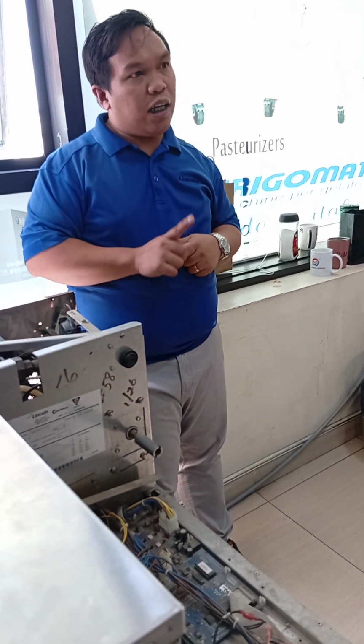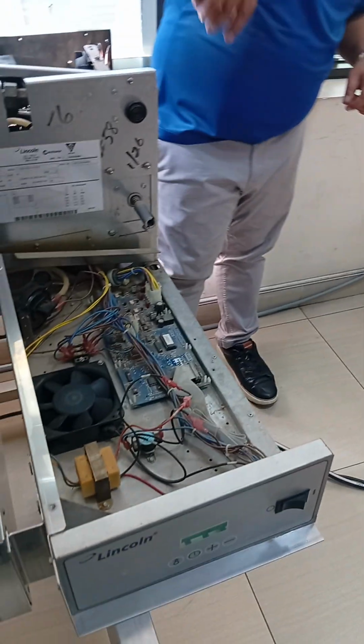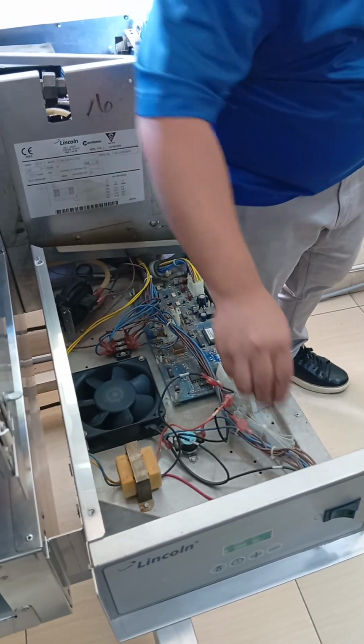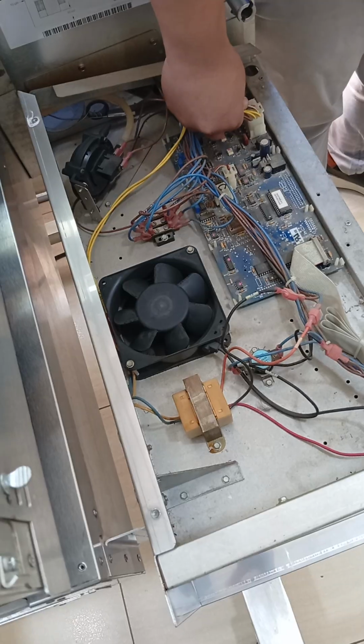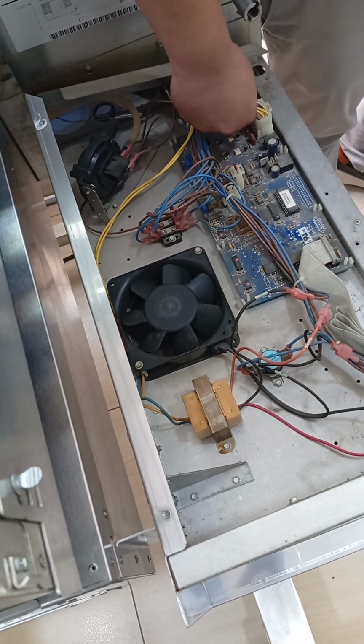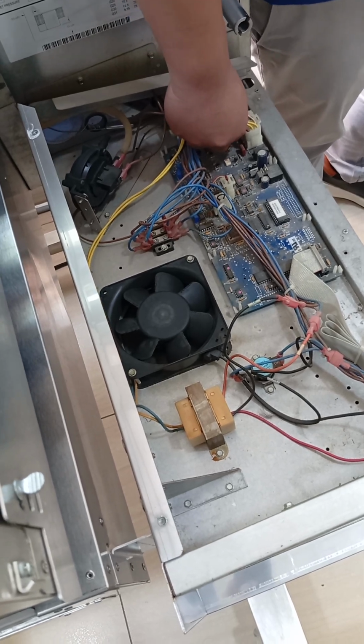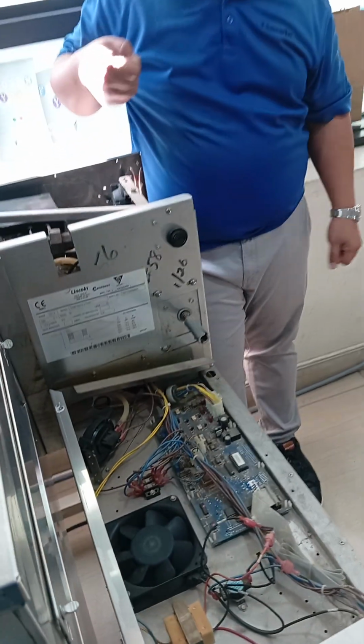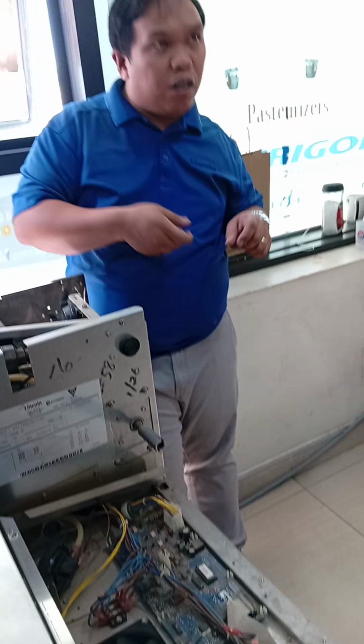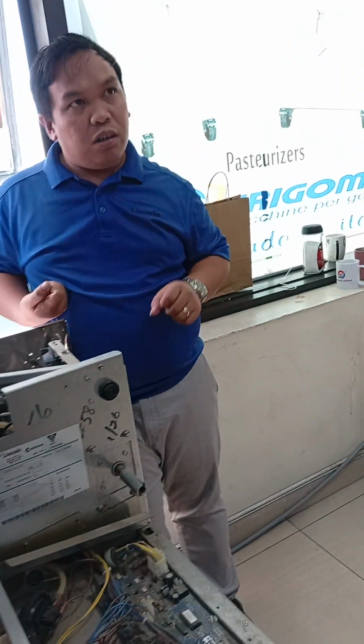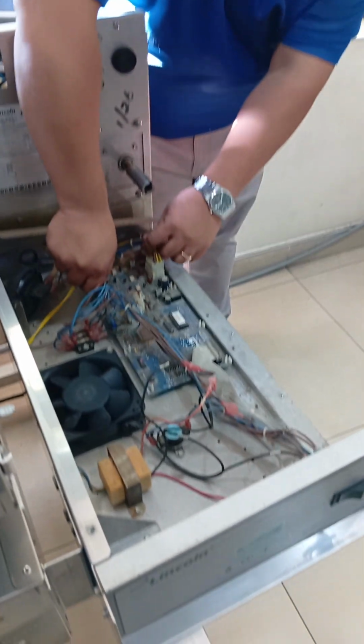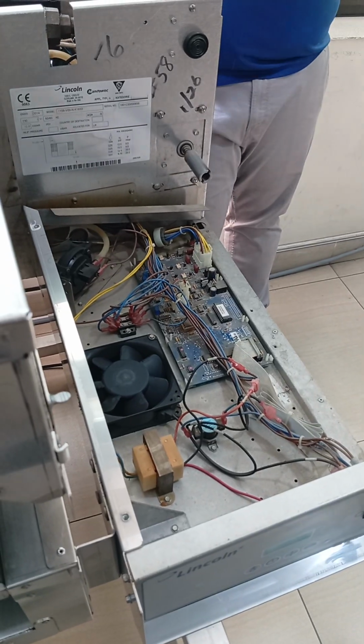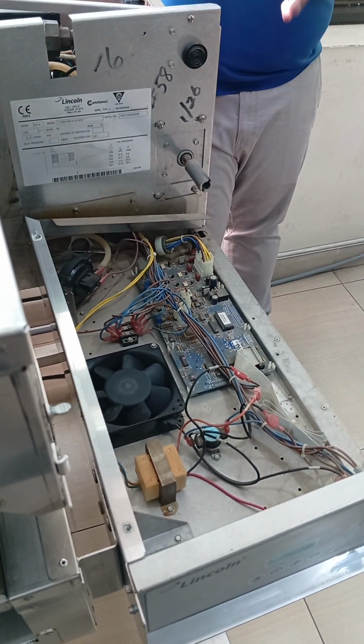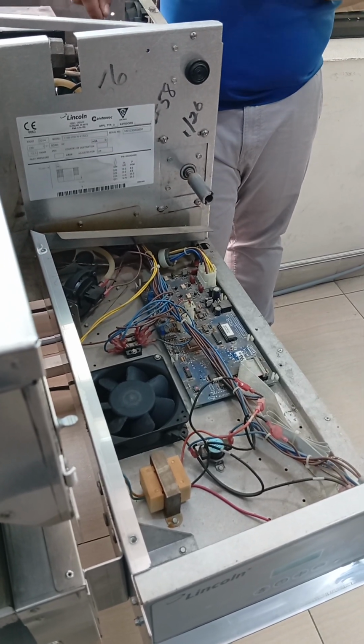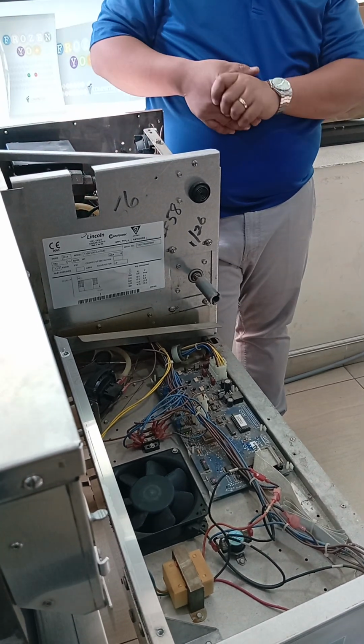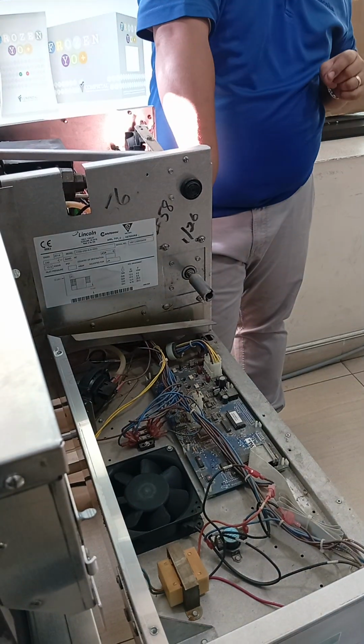Aside from the gas connection, we have some wires. Sometimes this wire is overtight, like this, because of some of the cable ties fixed from the factory. But remember, they are still human, so they might tighten too much. That's why the loop of the cable is too stressed or too stretched. What you can do is cut and make a proper loop. That's the initial inspection before you close the electronic compartment. And then, of course, before you do that, you should check your burner pressure to calibrate correctly.